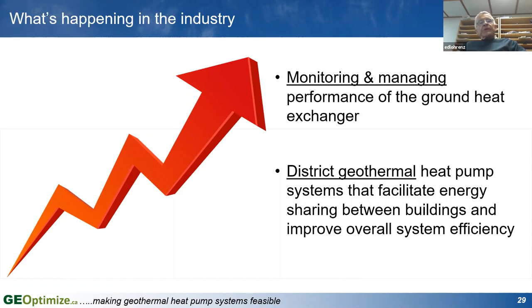Meanwhile, the apartment building next door is not going to start requiring a whole lot of cooling until people get home from work about 5 or 6 in the afternoon and they start cooking dinner and things like that. The load profile is different. So it's not the sum of the peak loads that you're looking at. What you're doing is looking at the peak load of the whole group of buildings at the same time. And you can also share energy. If you've got one building that's rejecting heat to the ground, and another building that's pulling heat from the ground, that can be beneficial to both.